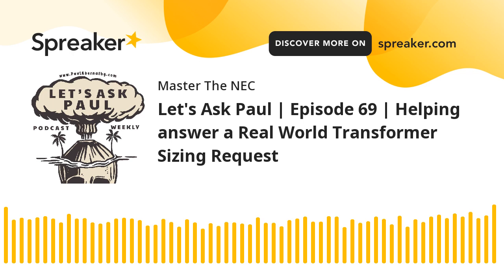Since we're going to stay in the transformer mode, it says, I know you are a busy person. If you are so inclined, here is the scope of the work. Okay, let me read this out totally here. It says, I have a 480 volt panel and I need to power a 208 volt HVAC unit. The full load of the unit is 78 amps. Okay, so we're going to go with that being the load. We'll assume this is all a nameplate. And it has a maximum overcurrent protected device of 100 amperes.